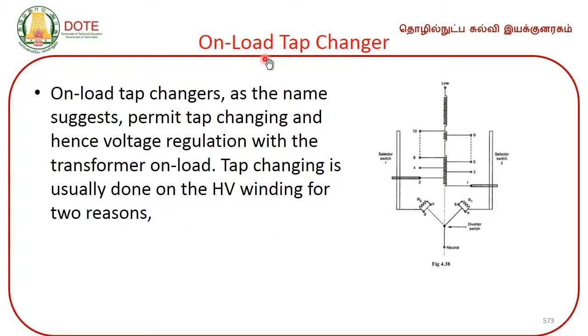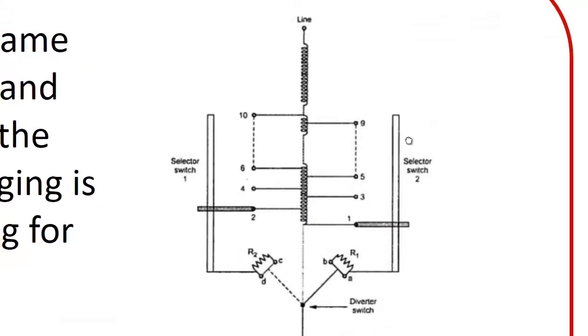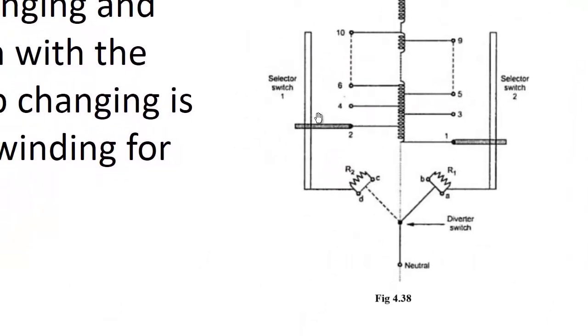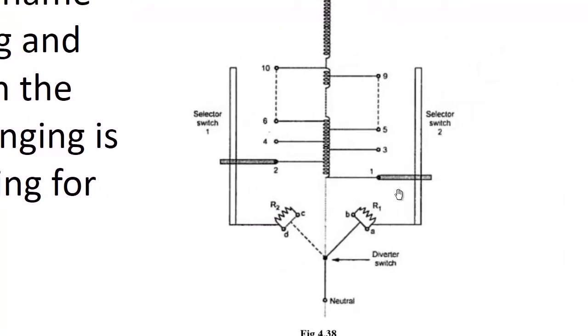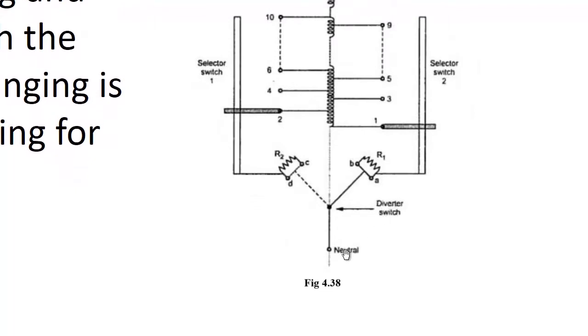Then the on load tap changer. On load tap changers, as the name suggests, permit tap changing and hence voltage regulation with the transformer on load. Tap changing is usually done on the high voltage winding for two reasons. So, this is the on load tap changer. Here there are two selector switches, 1 and 2, then this is the diverter switch.